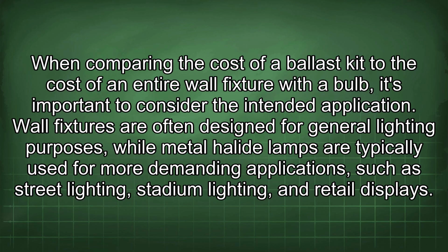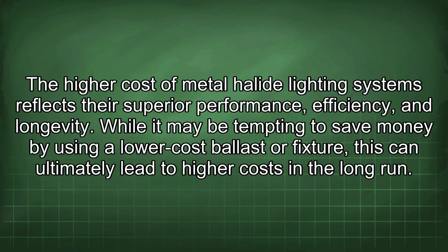Wall fixtures are often designed for general lighting purposes, while metal halide lamps are typically used for more demanding applications such as street lighting, stadium lighting, and retail displays. The higher cost of metal halide lighting systems reflects their superior performance, efficiency, and longevity. While it may be tempting to save money by using a low-cost ballast or fixture, this can ultimately lead to higher costs in the long run.